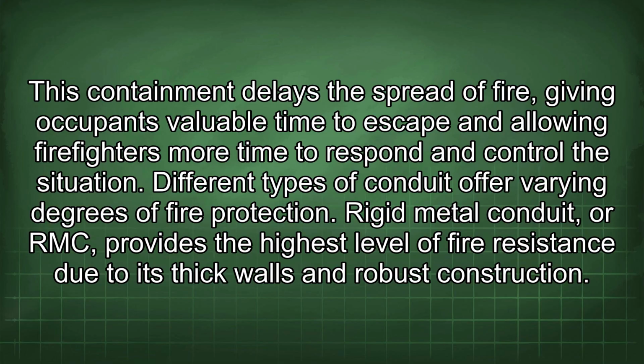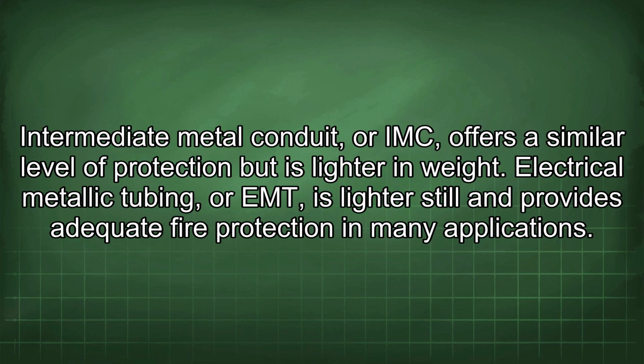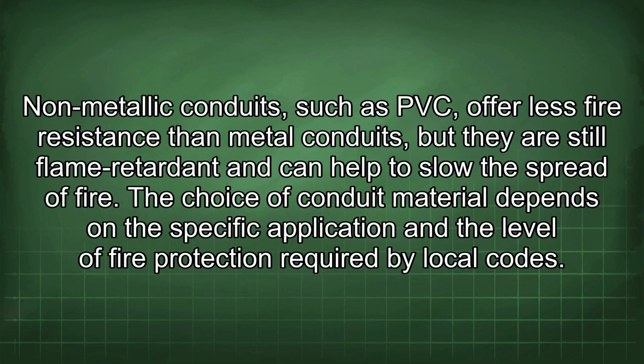Rigid metal conduit, or RMC, provides the highest level of fire resistance due to its thick walls and robust construction. Intermediate metal conduit, or IMC, offers a similar level of protection but is lighter in weight. Electrical metallic tubing, or EMT, is lighter still and provides adequate fire protection in many applications. Non-metallic conduits, such as PVC, offer less fire resistance than metal conduits, but they are still flame retardant and can help to slow the spread of fire. The choice of conduit material depends on the specific application and the level of fire protection required by local codes.